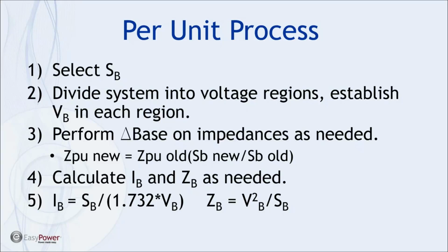Now, this is the shorter version of a change of base formula. There would also be a multiplier if the voltages were different. As you change per unit impedance on a transformer from one base to the other, if the voltages vary slightly, it also changes the percent impedance by the square of the voltage change. Most of the time, I try to keep the systems pretty simple, so we don't incorporate a voltage change. This formula is a simplified version of it, and that's what we'll stick with.